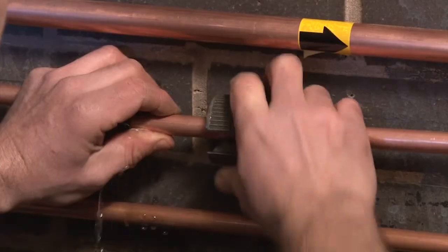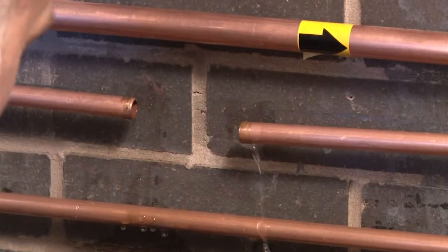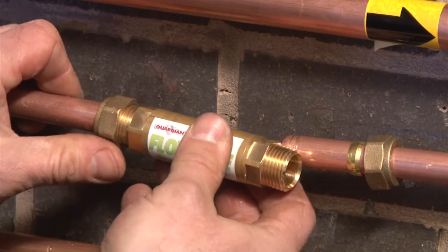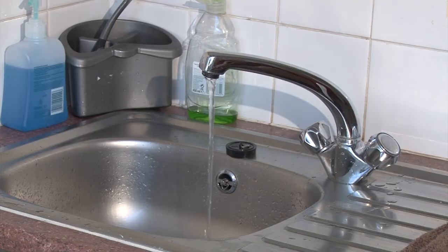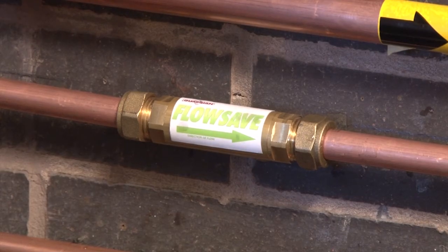The FlowSave is an easily installed in-line valve which, when fitted to the domestic hot water pipe of a combination boiler, reduces the flow of water to 3 litres a minute until a temperature of 42 degrees has been reached. This not only allows for saving in water but also the gas needed to heat it. With no serviceable parts, simply fit and forget.